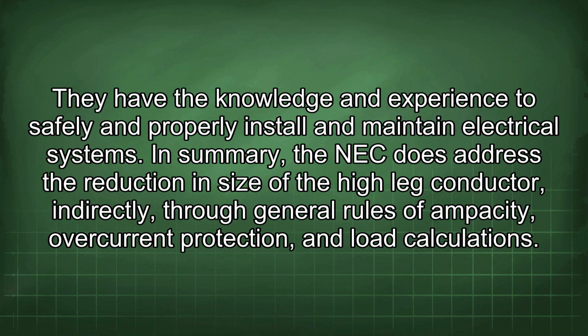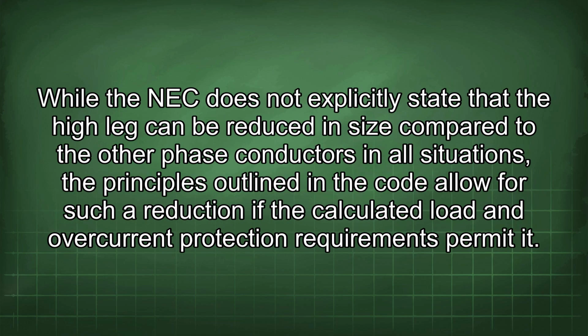In summary, the NEC does address the reduction in size of the high-leg conductor indirectly through general rules of ampacity, overcurrent protection, and load calculations. While the NEC does not explicitly state that the high leg can be reduced in size compared to the other phase conductors in all situations, the principles outlined in the code allow for such a reduction if the calculated load and overcurrent protection requirements permit it.